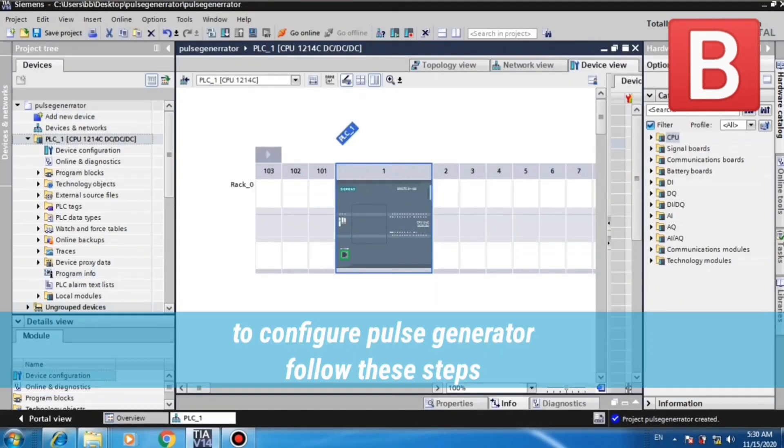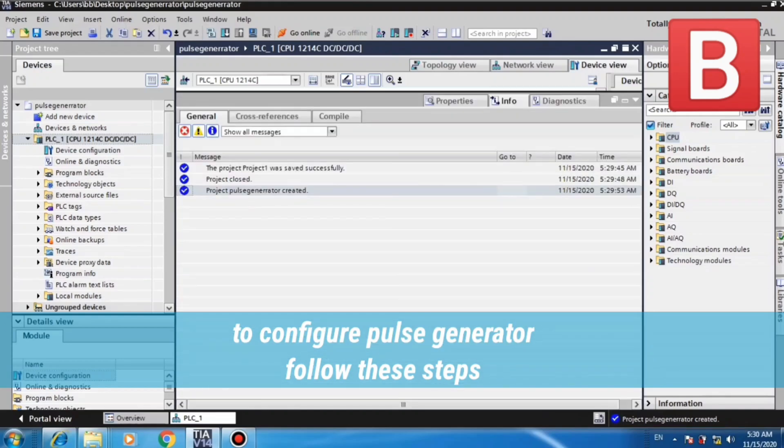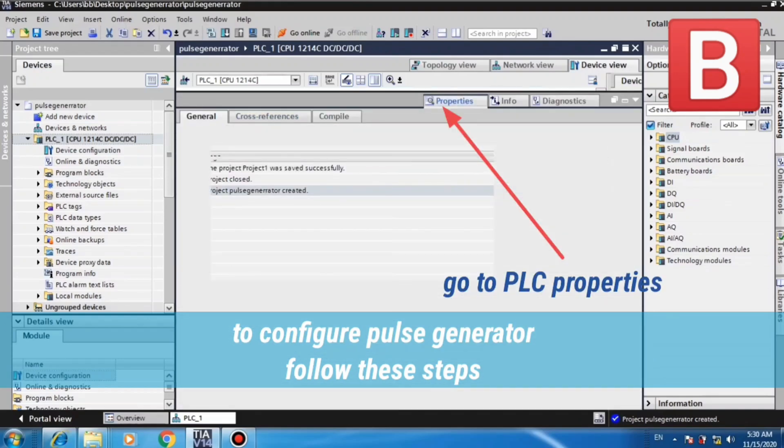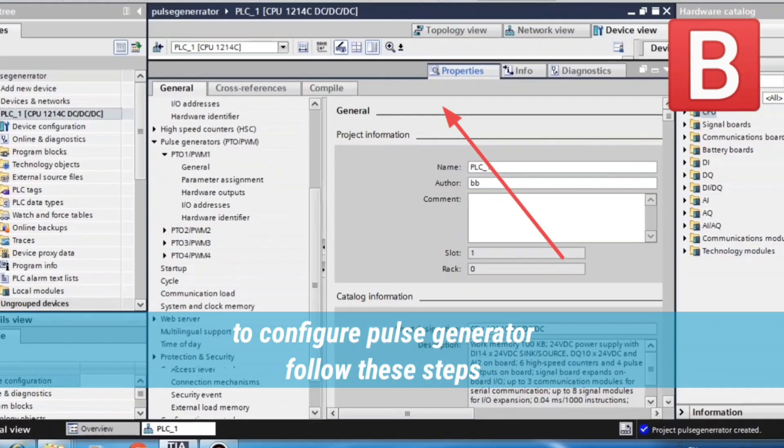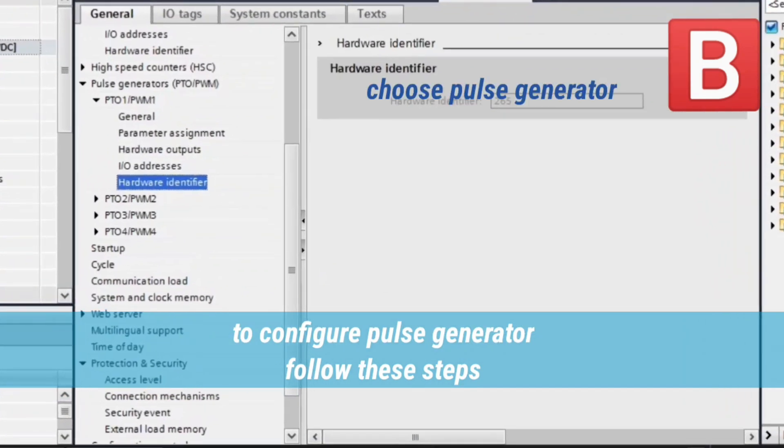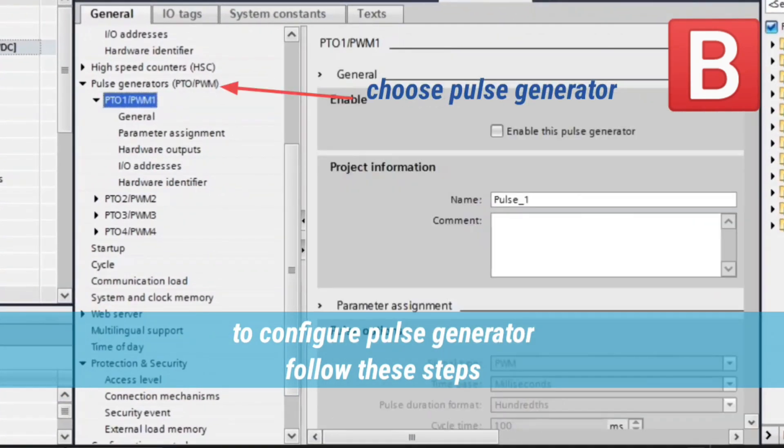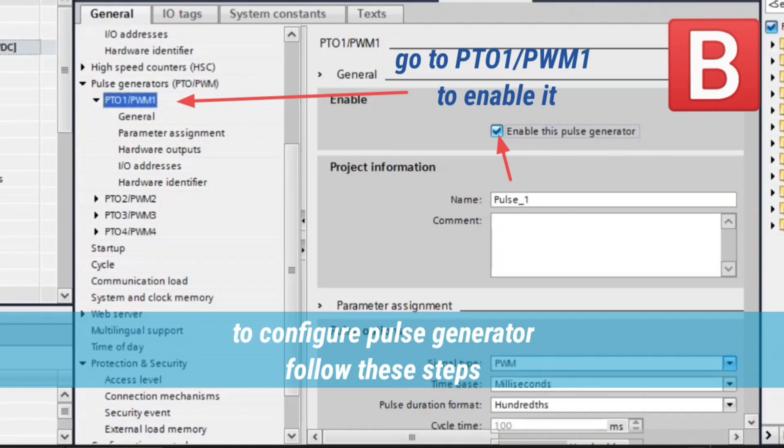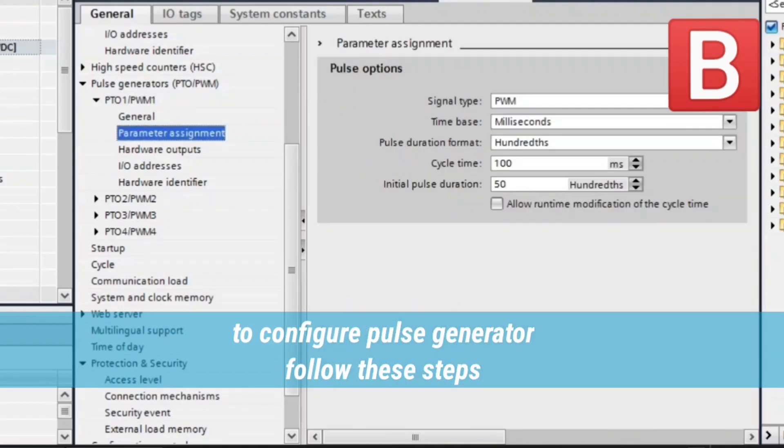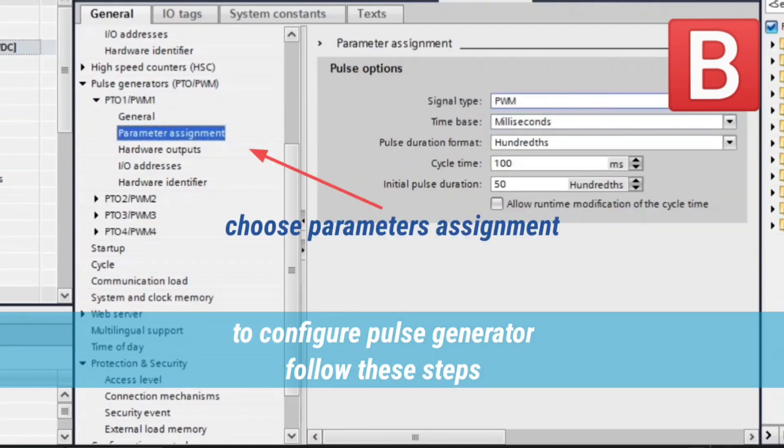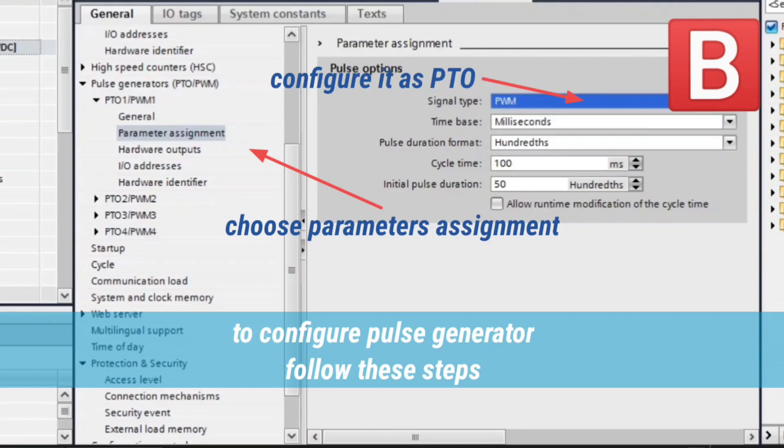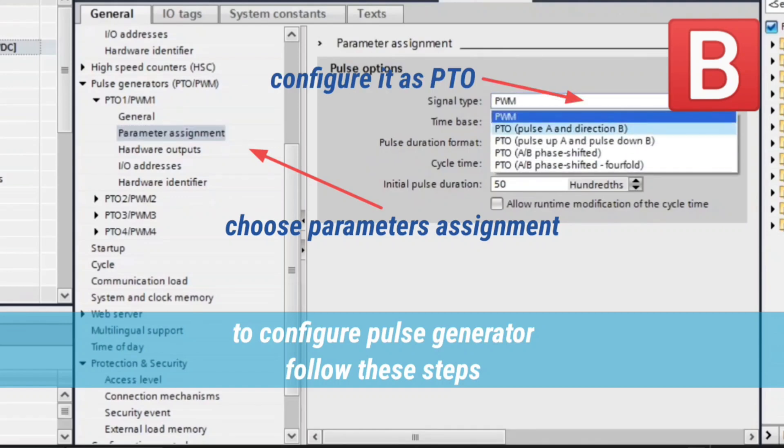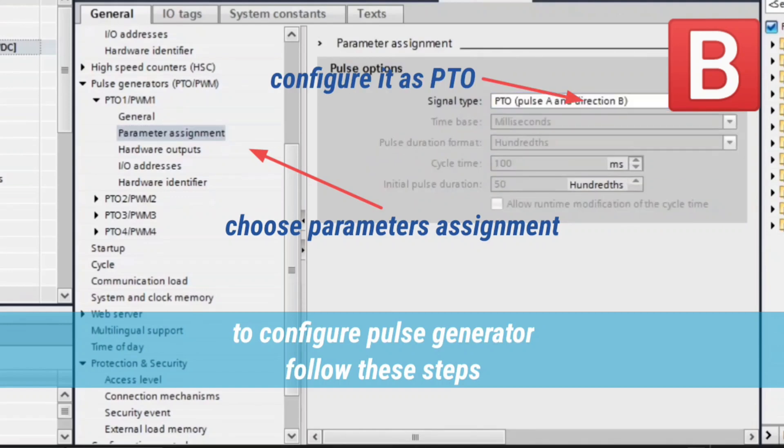Now we will configure the pulse generator. Go to PLC Properties, choose Pulse Generators. Go to PTO1PWM to enable it by marking this small box as shown. Choose Parameters Assignment, configure it as PTO.